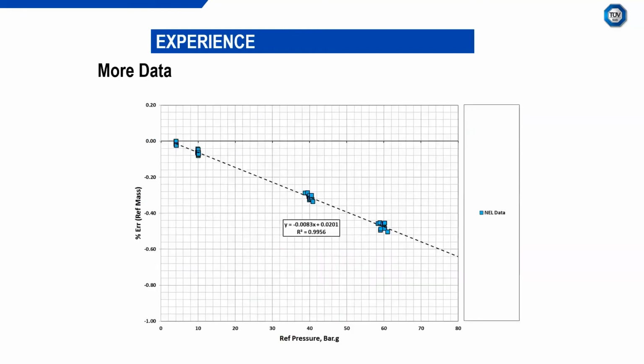This is another Coriolis flow meter, so it's a different size, different manufacturer, different shape as well. And you can see, again, we've got a constant linear effect. Not quite as significant as the previous device. You can see at 60 bar, it's close to about a 0.5% underread, but again, it's a linear pressure effect. Linear is good news because it means it's easily corrected. So that's just some more data on another Coriolis meter.